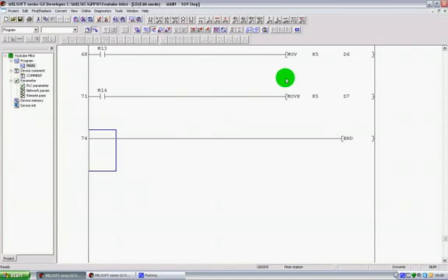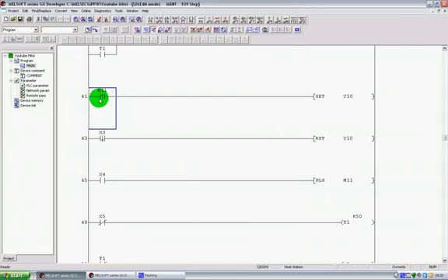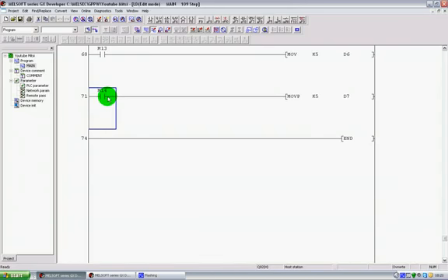Now I'm not going to run this one under the simulation because the only difference here is this P at the end of the move command. You'll see that we've just got move here and we've got move here, but the P basically means pulse. This just makes this particular command stable and operate only once, and it only works once on the initiation of this going high. So it's very much like using this trigger here, which is the leading edge trigger, and we've just pulsed it, and then we just do a quick pulse move.